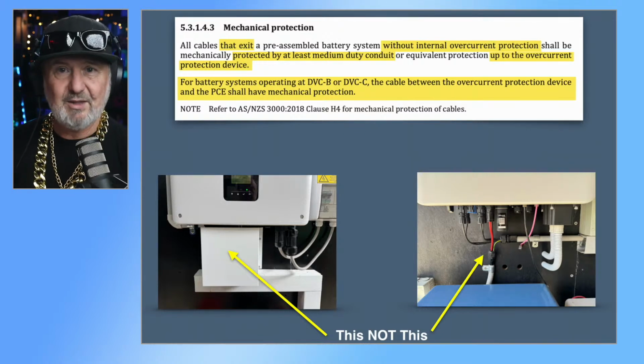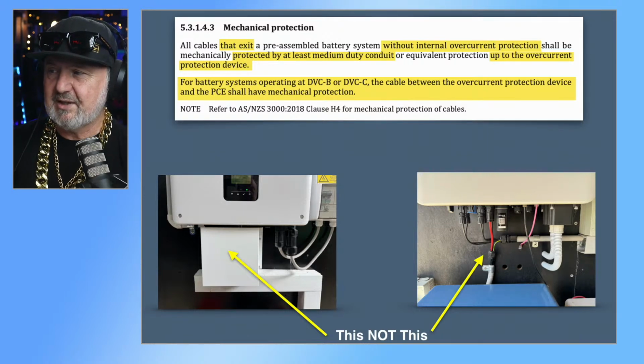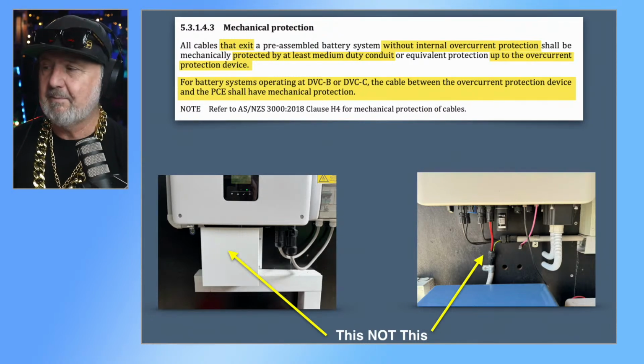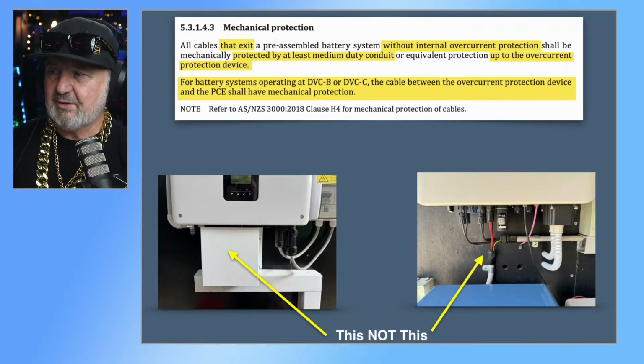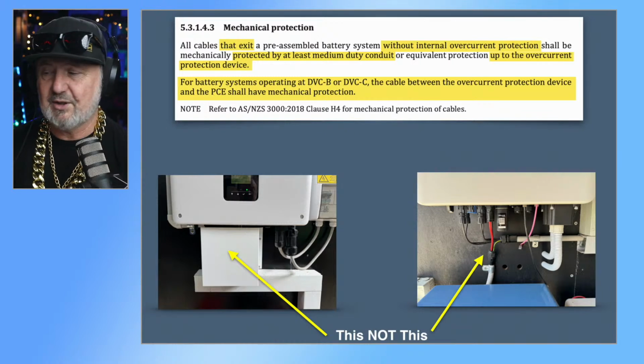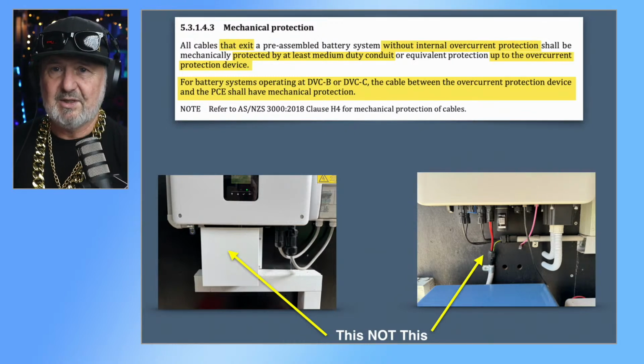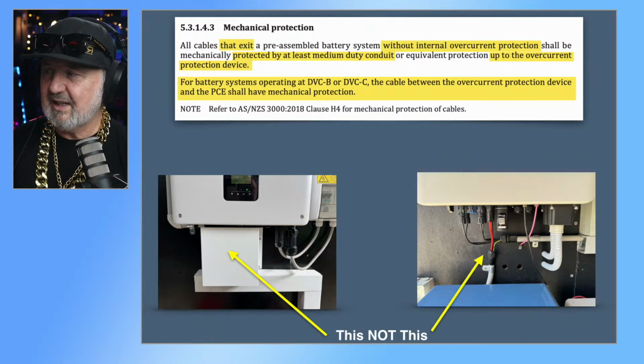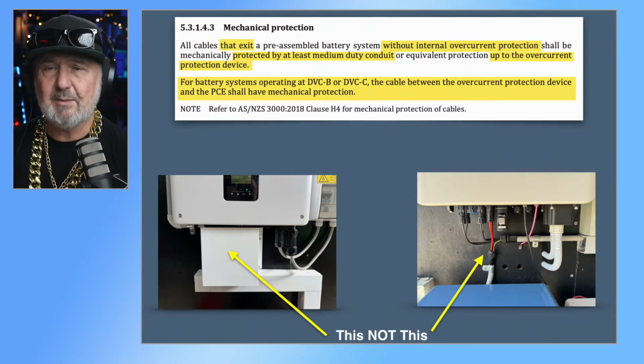But the wording for the battery system is, all cables that exit a pre-assembled battery system without overcurrent protection shall be mechanically protected by at least medium duty conduit up to the overcurrent protection device. Okay. And then it goes on to say, for battery systems operating at DVC B or C, and in this case, the picture I've shown is a battery system that's DVC C, the cables between the overcurrent protection device and the PCE shall be mechanically protected.